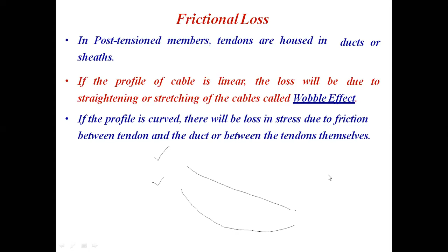The strand will twist. That effect is called the wobble effect, and it occurs when the cable is linear. The second case is when the profile is curved. When the profile is in the form of a curved shape, the losses take place due to friction developing between the strand and the duct, the strand and the sheathing pipe. These are the two frictional losses.